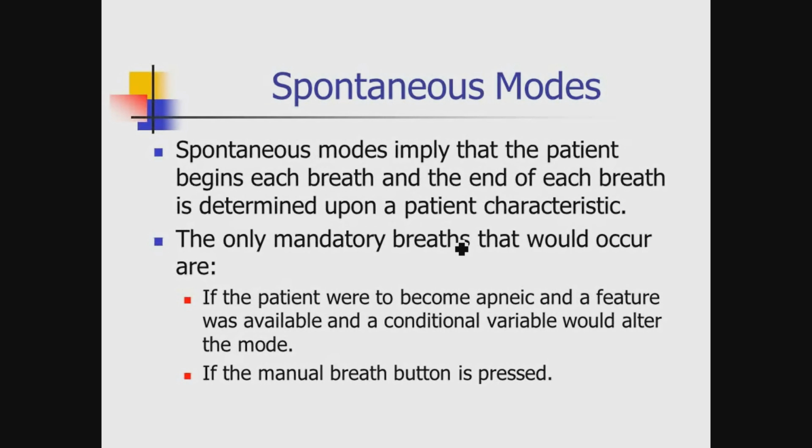The only time you would see a mandatory breath occur during a spontaneous mode is if the patient went apneic. So if I had a patient who was perhaps a drug overdose, and they're breathing spontaneously, but periodically they just stop breathing, it would be nice for the ventilator to recognize that, alarm, and kick into an apnea ventilation until they started breathing again.